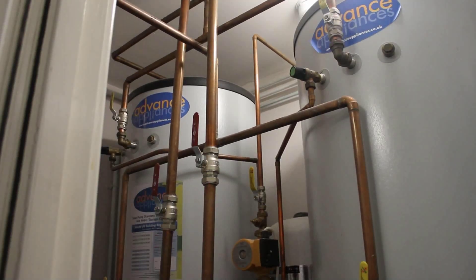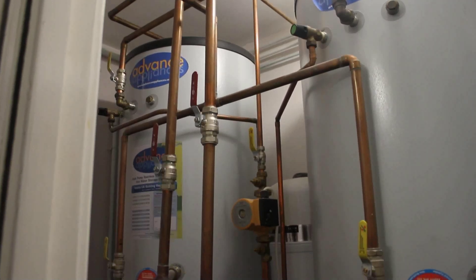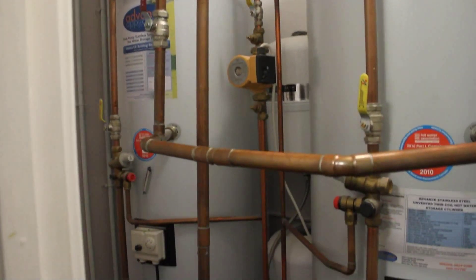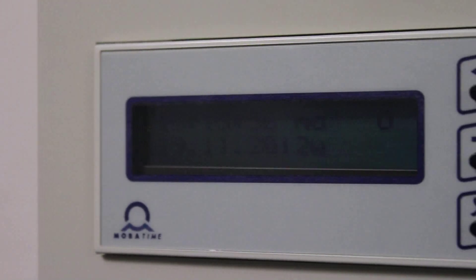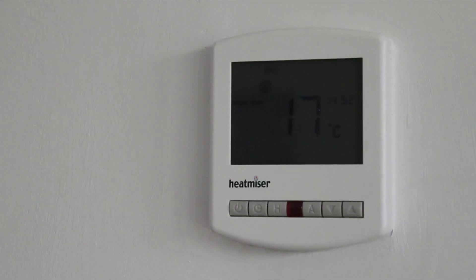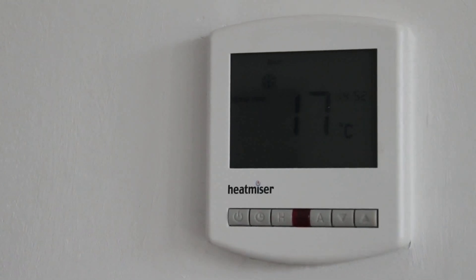The ventilation system also retains heat through a heat exchanger and recovers that warmth. The air source heat pump is an eight kilowatt unit designed to supply hot water for space heating and for showering. A heat pump uses one-third of the energy of a traditional electric system. The underfloor heating is particularly appropriate — we wanted a background temperature of about 17 degrees, but when people start using the space, the temperature can be brought up very quickly.